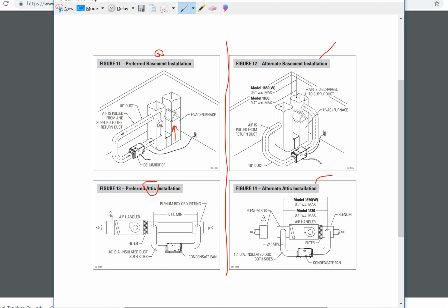On the alternative, which is return to supply, usually that's done when there's space restrictions, where you can't get this required 6 feet that you have to have between the two branches here. When you can't get 6 feet of clearance within a room or a space or an attic, then you can always find a way to get something tied to the return and something tied to the supply. So that's one of the drivers of why to utilize the return to supply configuration. But the fans can be in conflict. That's why there's requirements that say that you have to have airflow that's within a pressure range.